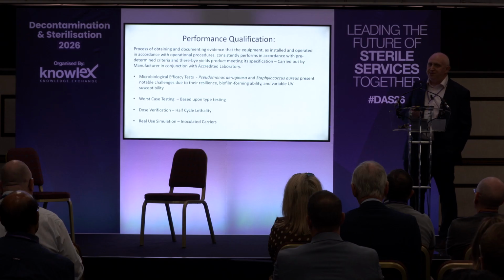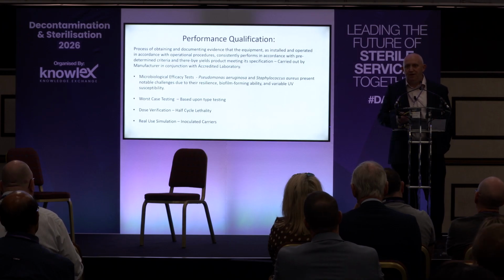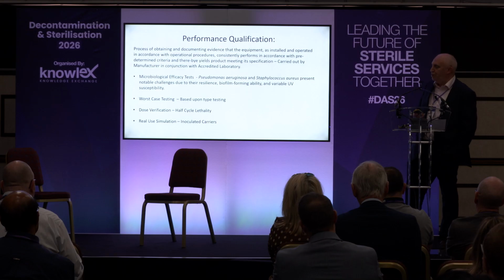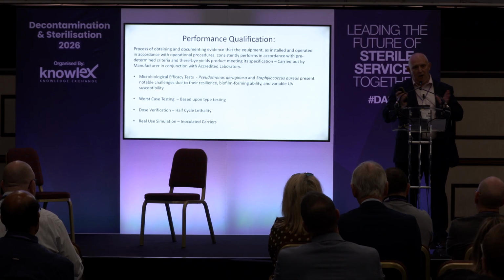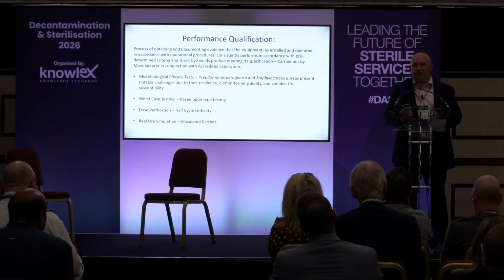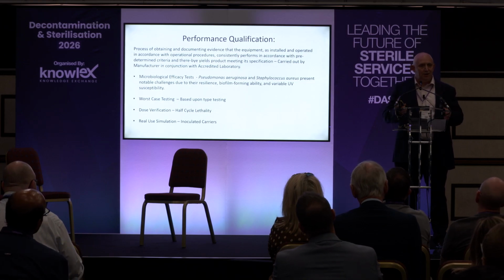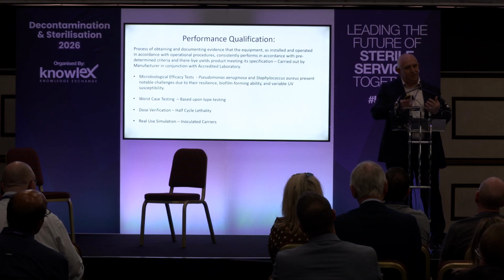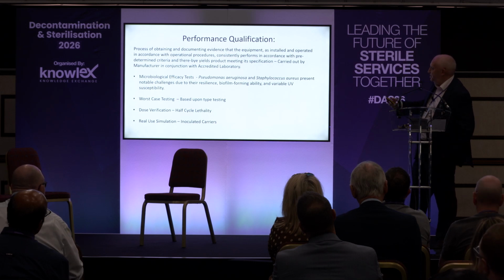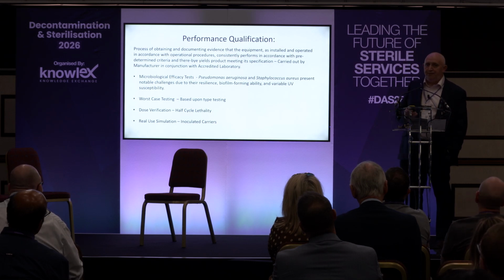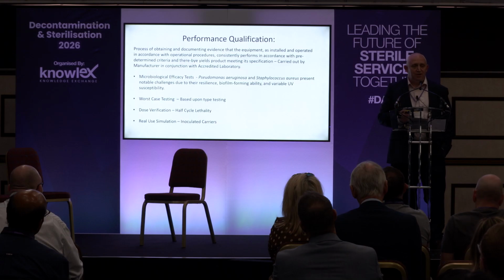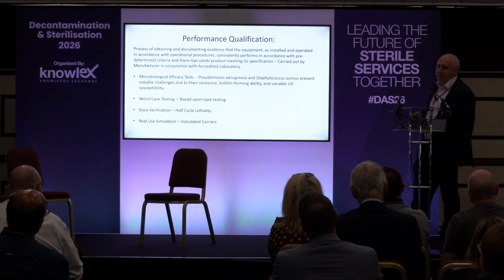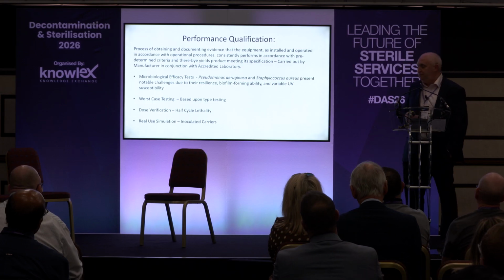So when we look at worst case testing and in other areas of sterilisation and decontamination, we go through what they call half cycle lethality, where we actually halve the exposure. So as an example, it could be a 10-minute hold time on an ethylene oxide sterilisation process. They halve it to 5 minutes. That is something that we may need to look at with this type of technology. We either halve the amount of dose, so we disengage a number of the lamps, or again, we halve the exposure time. Something that needs to be looked at, I think, as part of the validation.